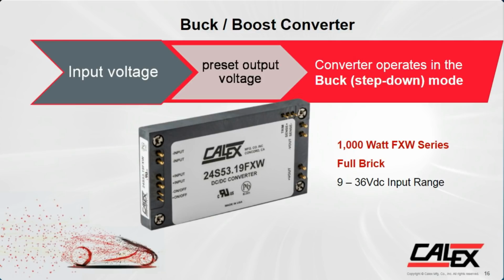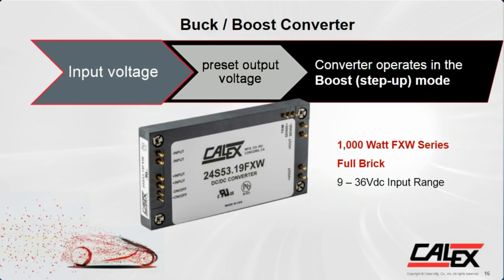Most converters can work in boost and buck mode, they're just not bidirectional. You'll hear these terms applied to a converter like our brick here, which has a 4-to-1 input ratio - a 9 to 36 input range, that's where the 4-to-1 comes from. This can operate in buck and boost mode, but it can't change current direction.